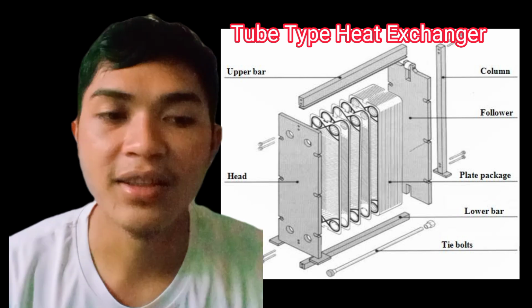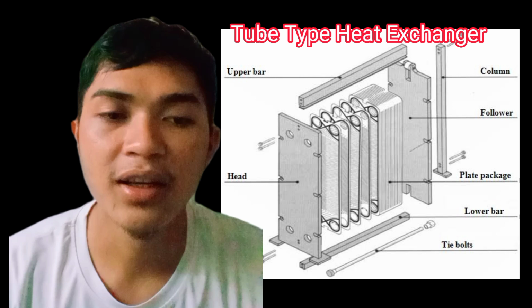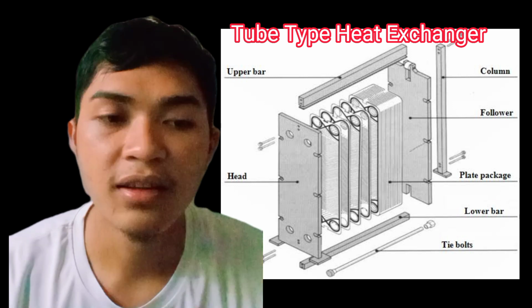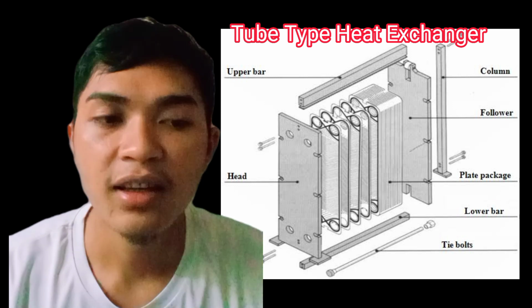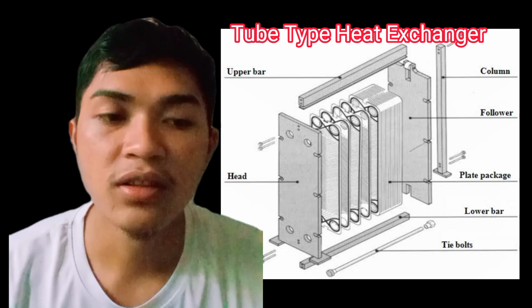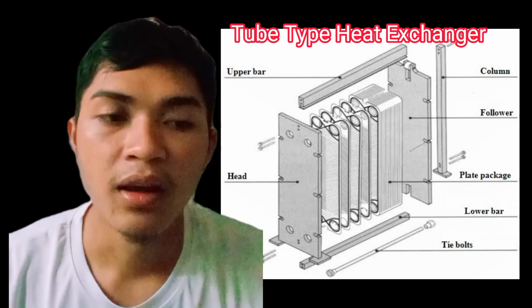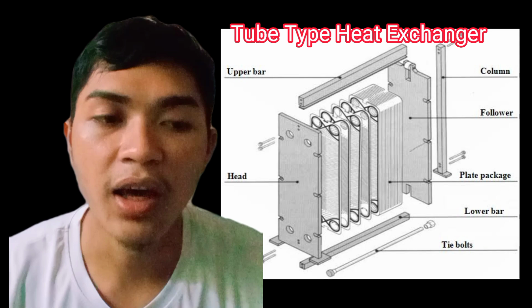While tightening the plates together, care must be taken for even tightening of all the exchanger studs and bolts, or else leaks will occur. Those are the procedures in maintaining and cleaning of tube type and plate type heat exchangers.